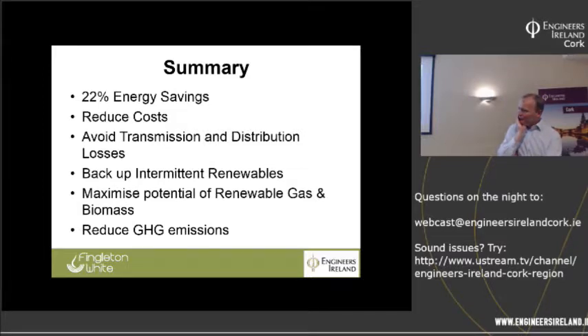Will the system run at maximum output in the domestic scale? Yes, all the time. And that's why it needs an export tariff, because at 2 kilowatts you'll be exporting a lot of your electricity. If you're not getting paid for that, you're buying gas to generate that electricity, and if you're not getting paid for it, it's pointless. So it's sized around the heat load.